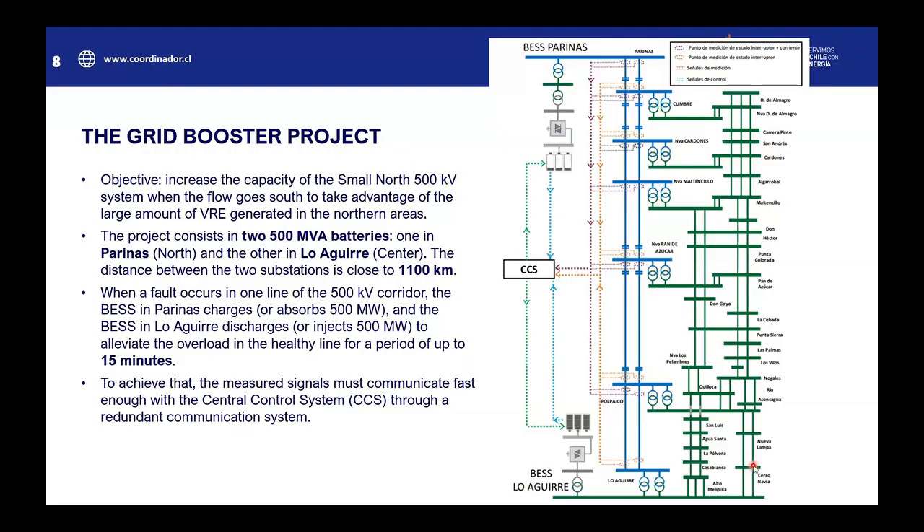The Grid Booster project's objective is to increase the capacity of the small north 500 kV system when the flow goes south, to take advantage of the large amount of VRE generated in the northern areas. The project consists of two 500 MVA batteries, one in Parinas and the other in Lo Aguirre in the center. The distance between the two substations is close to 1,100 kilometers.